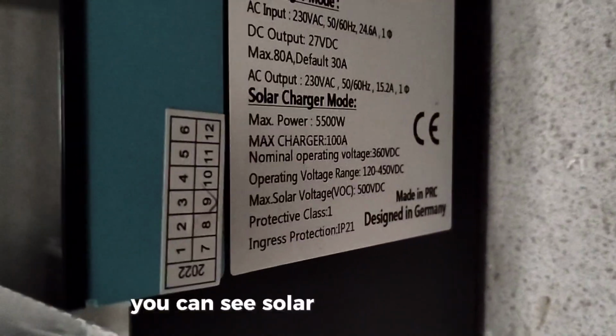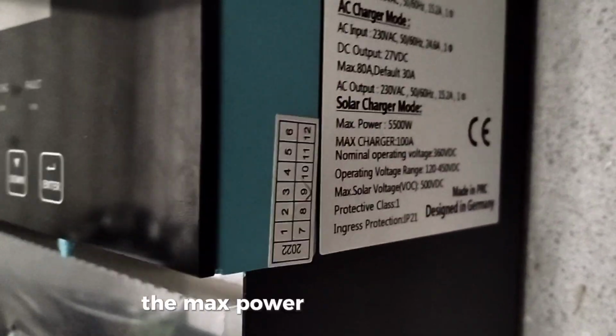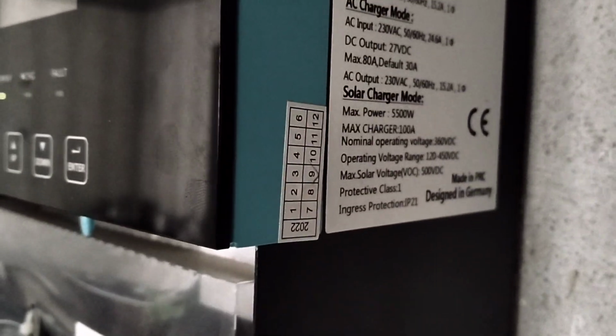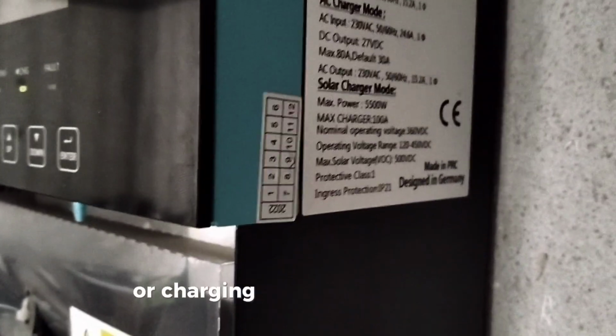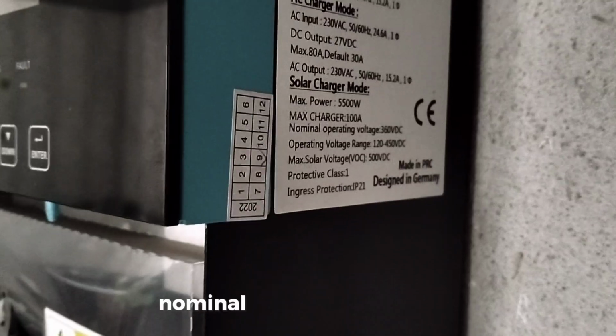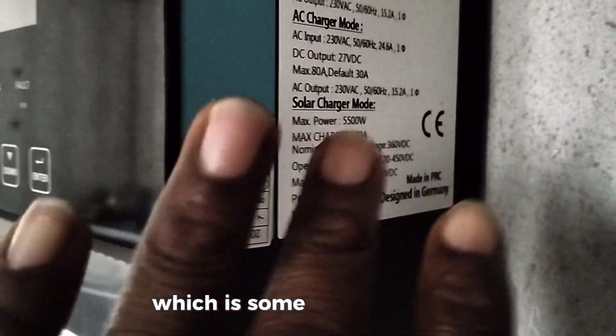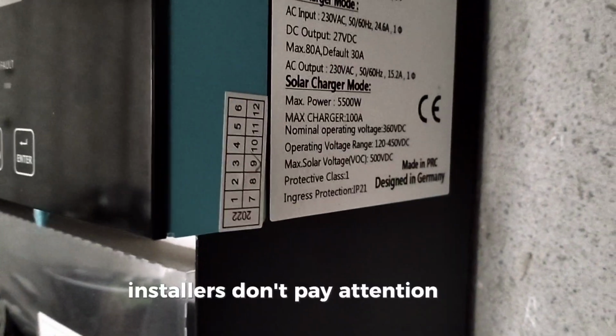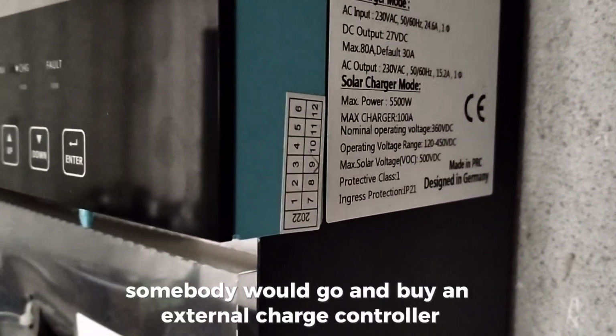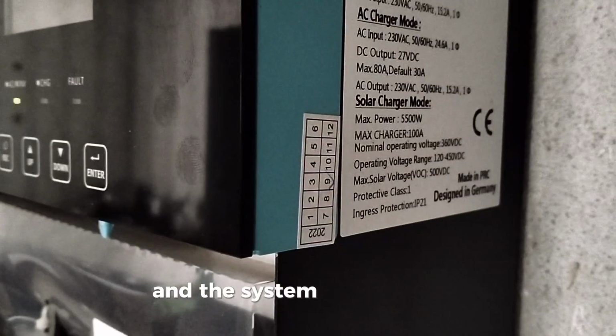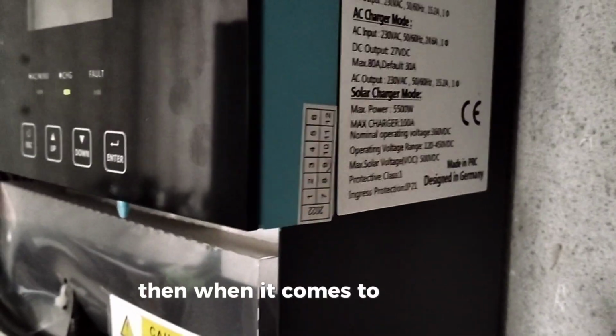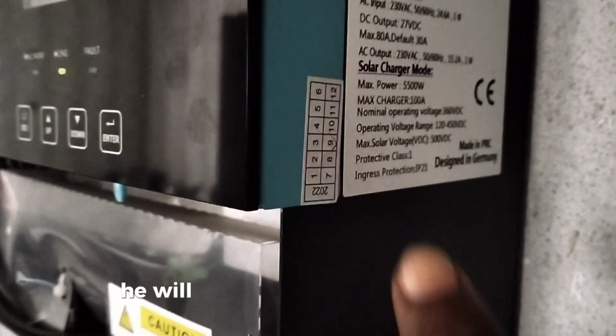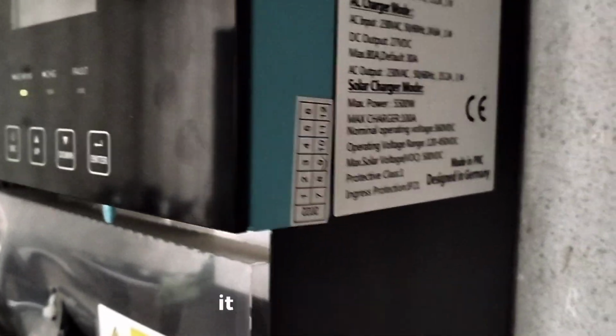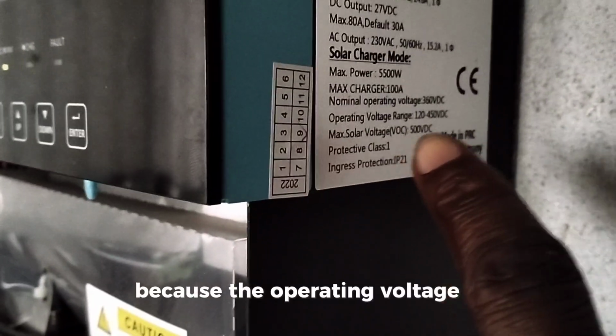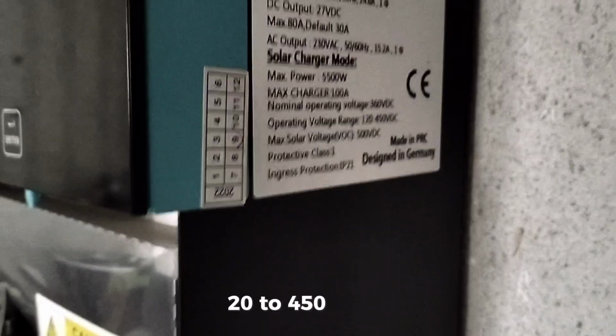You can see the solar charger mode: max power is 5,500 watts, max charging current is 100 amps. Then there's the nominal operating voltage, which is something installers often don't pay attention to. Someone might buy an external charge controller and do 2 series, and the system charges normally. But with a solar hybrid, if they don't pay attention and do 2 series on this inverter, it won't work, because the operating voltage range is 120 to 450 volts.